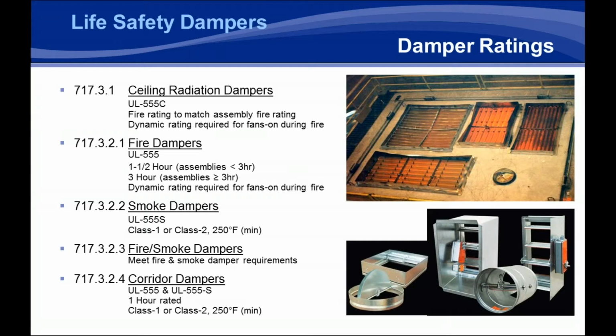Now, the Uniform Mechanical Code requires that air handlers or air distribution units that provide more than 2,000 CFM shut down in an emergency, but anything less than or equal to 2,000 CFM doesn't have that requirement. Typically in, say, multifamily housing, what you would find is these smaller units supplying or bringing return air through a rated ceiling. The problem with that is any penetration of a rated ceiling needs to be protected by a ceiling radiation damper. But as the air handler is not shut down in these emergency situations, you then need a dynamic damper to close under that airflow.